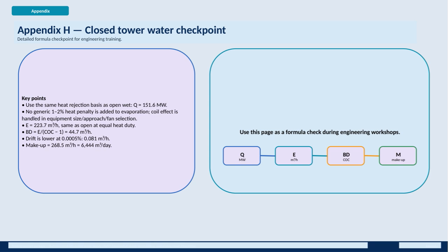Drift losses are minimized in this closed system, with a very low rate of only 0.0005% or 0.081 cubic meters per hour. Finally, the makeup water requirement totals 268.5 cubic meters per hour, which translates to about 6,444 cubic meters per day. This page is really useful as a formula check during training workshops to ensure our engineering calculations are aligned and accurate, especially when dealing with closed tower water systems in a complex cooling and desalination environment.